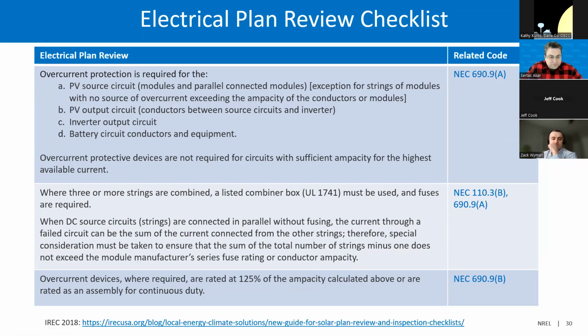And some more electrical requirements: overcurrent protection is required for PV source circuits, PV output circuits, inverter output circuits, and battery circuit conductors and equipment. The overcurrent protective devices are not required for circuits with sufficient ampacity for the highest available current. Where there are three or more strings combined, a combiner box listed to UL 1741 must be used, and fuses are required. When the DC source circuits are connected in parallel without fusing, the current through a failed circuit can be the sum of the current from the other strings.